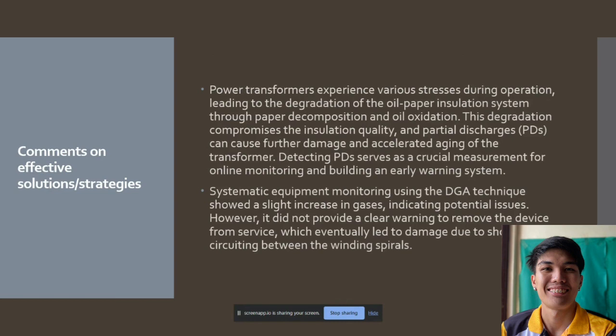Comment on effective solutions and strategies. Power transformers experience various stresses during operation, leading to the degradation of the oil paper insulation system through paper decomposition and oil oxidation. This degradation compromises the insulation quality, and partial discharges cause further damage and accelerate aging of the transformer. Detecting PD serves as a crucial measurement for online monitoring and building an early warning system. Next, systematic equipment monitoring using the DGA technique showed a slight increase in gases indicating potential issues. However, it did not provide a clear warning to remove the device from service, which eventually led to damage from a short circuit between the winding spirals.